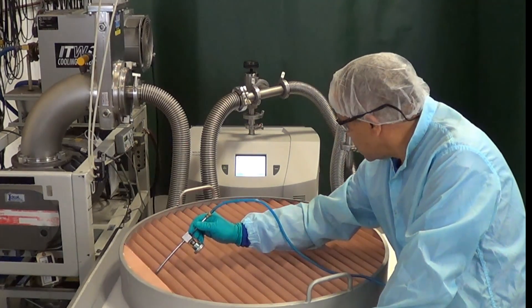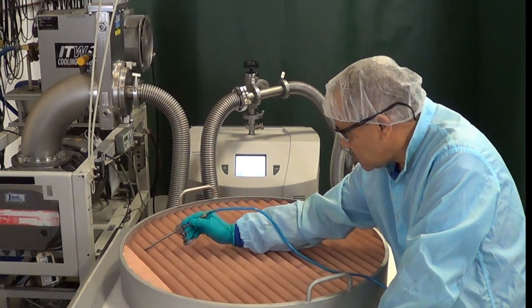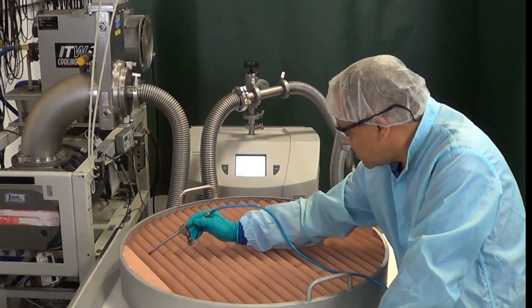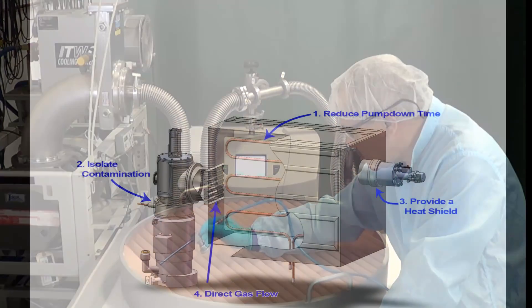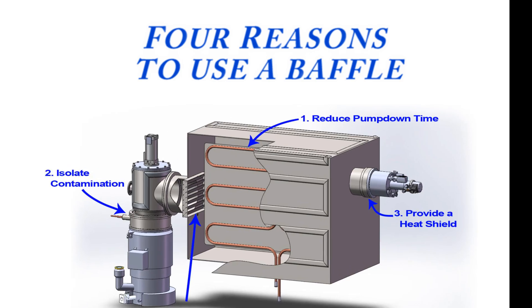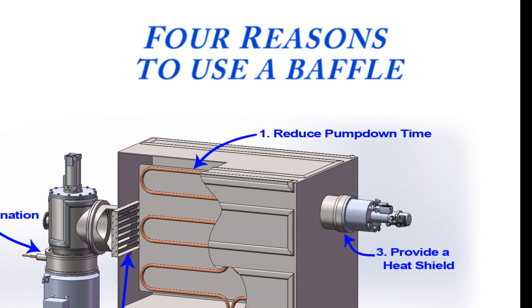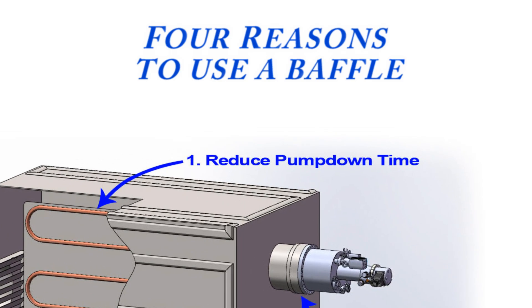Vacuum baffles and cold traps are important components of many vacuum systems. There are four reasons these products are often used. First, a cryo coil or baffle can reduce the pump-down time of a chamber by as much as seventy-five percent.